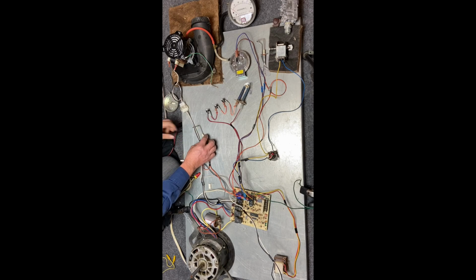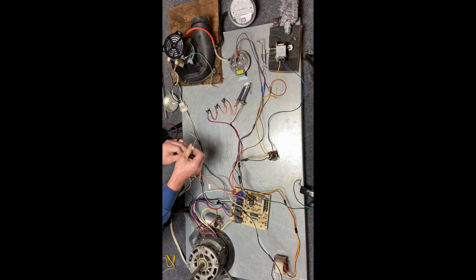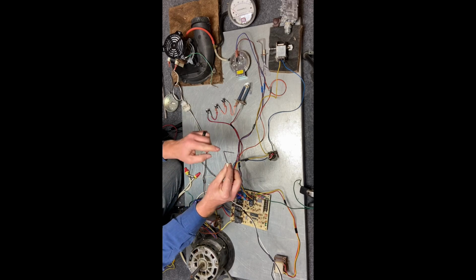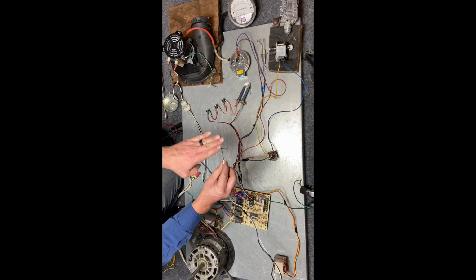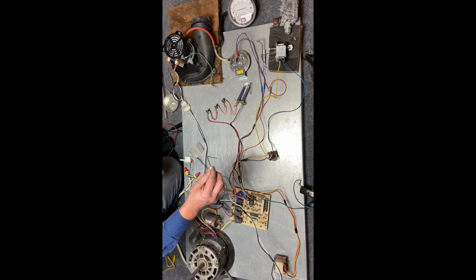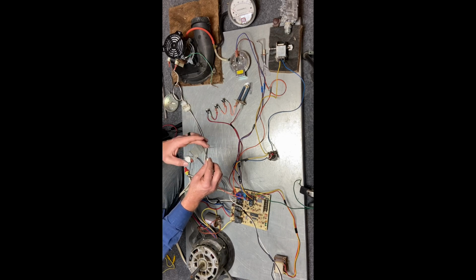They notoriously get dirty, and if we look at this flame sensor right here, there's a lot of buildup on here. See, it's nice shiny metal, and here it discolors. As the flame burns across this, any of the dust that's in the air, the flame itself burning causes a buildup on this. What we want to use is a type of Brillo pad or abrasive pad to clean that off. Never use sandpaper because the sandpaper actually has the glass that can leave residue on here that actually turns to a glass coating. The sand from the residue turns to a glass coating, and it can give us a coating on there that doesn't allow the flame rectification to work.